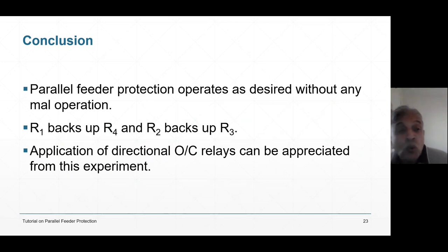What is the conclusion of the experiment? Parallel feeder protection operates as desired without any maloperation. R1 backs up R4 and R2 backs up R3. Yes, sir, that we have seen by our eyes. This we have wired ourselves. You see, most of the experiment is permanently wired. What all we have to wire is some fault resistance and some load resistance only.